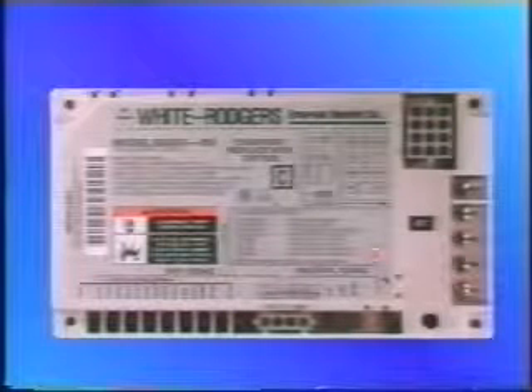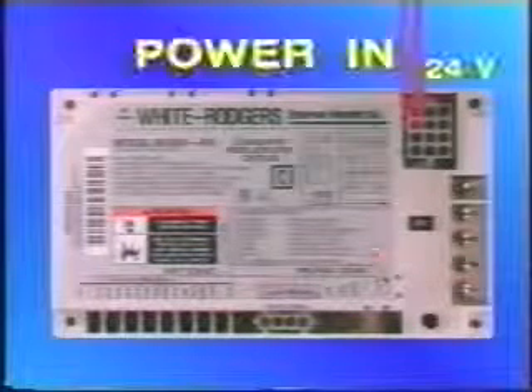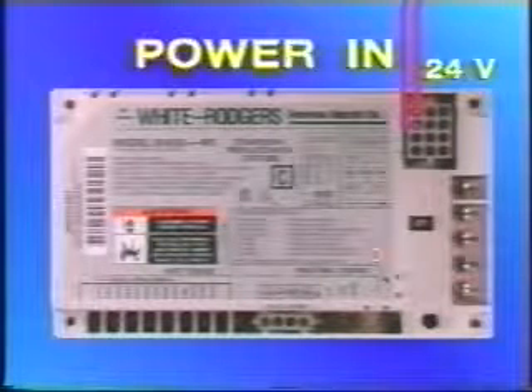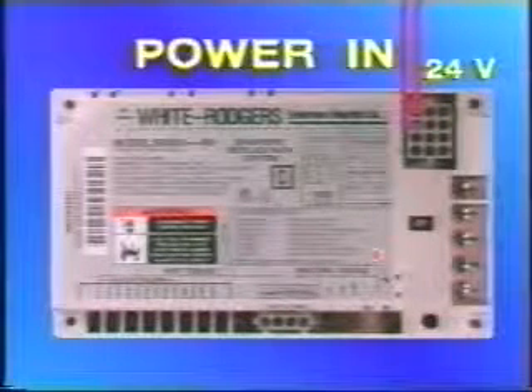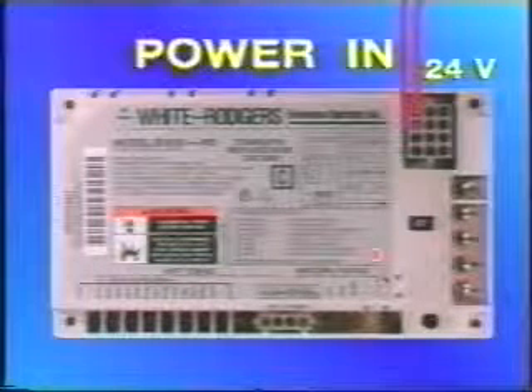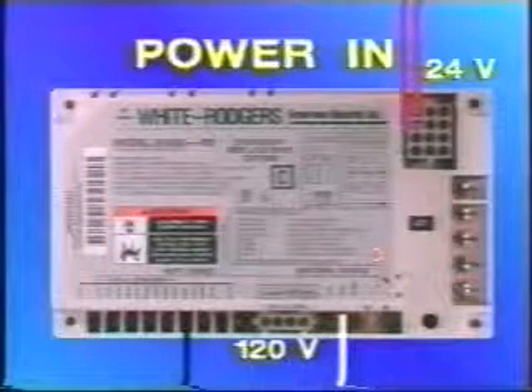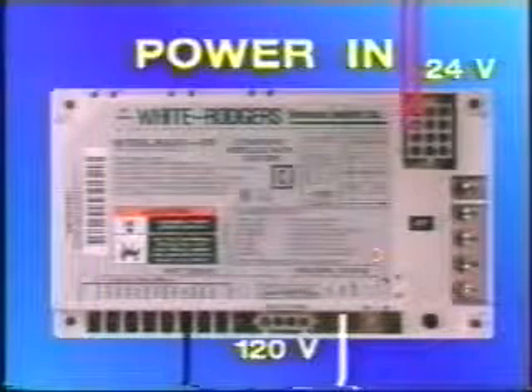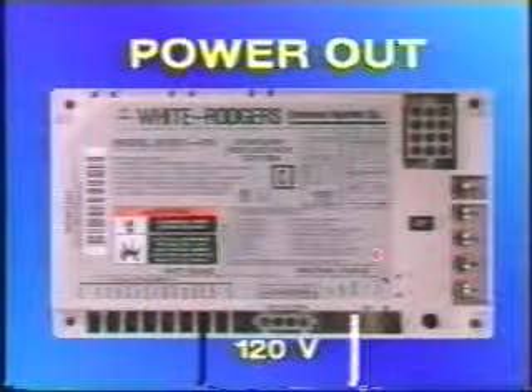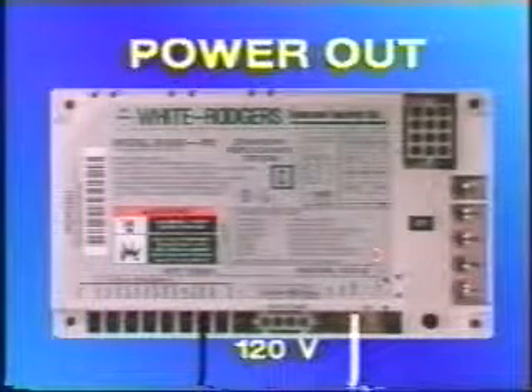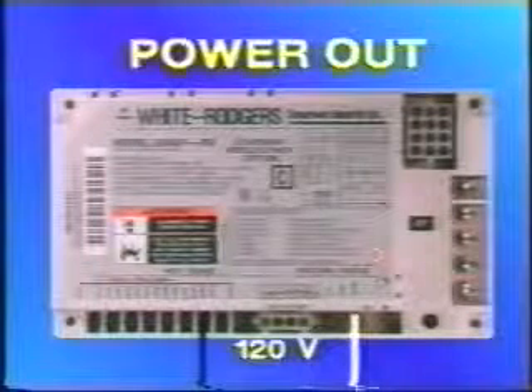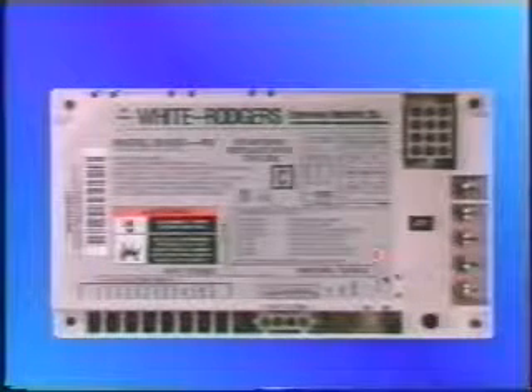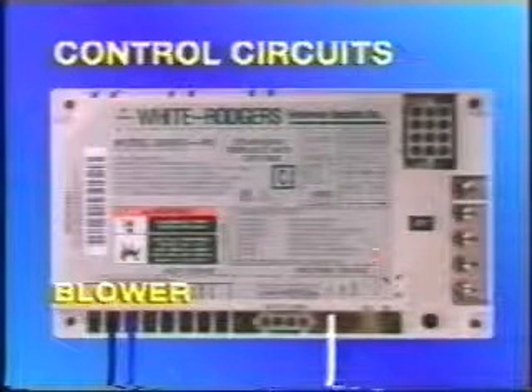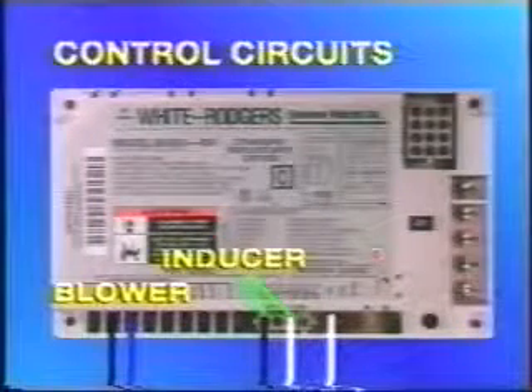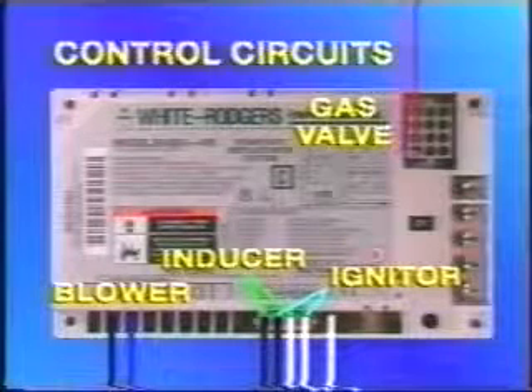The terminals can be divided into 5 categories. First are the terminals that are used to bring power into the module. 2 voltages are used, 24 volts for control circuits and 120 volts to power line voltage components. 2 terminals are used to deliver unswitched power out of the module. These are the 2 120-volt terminals that power the primary side of the transformer. Next are the terminals that directly cycle system components. These are the blower motor, the inducer motor, the igniter, and the gas valve.